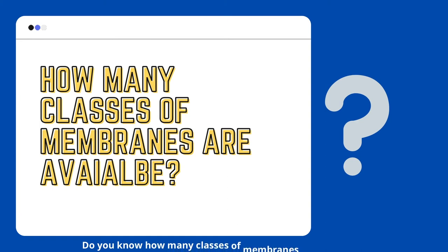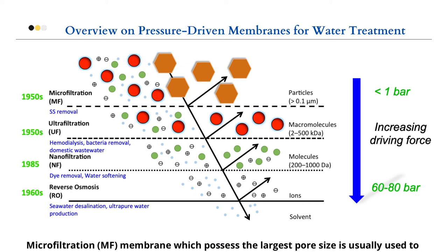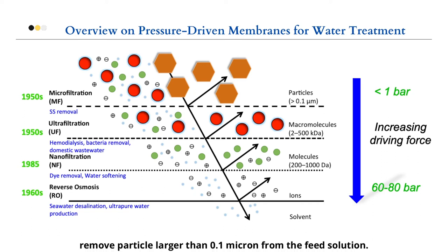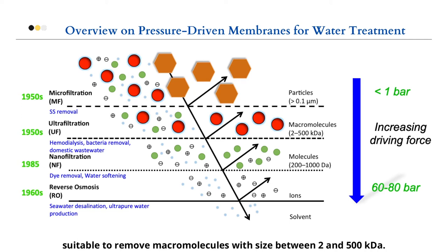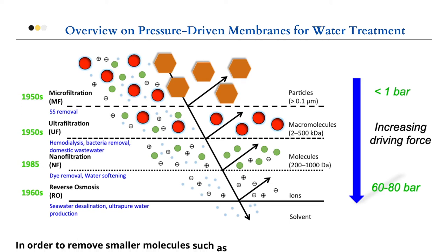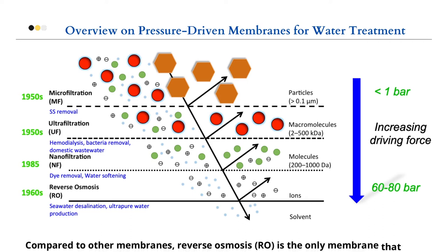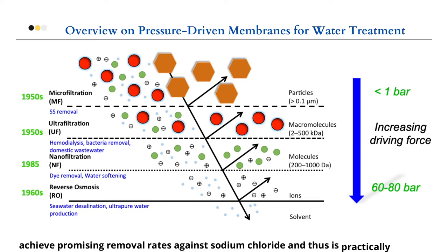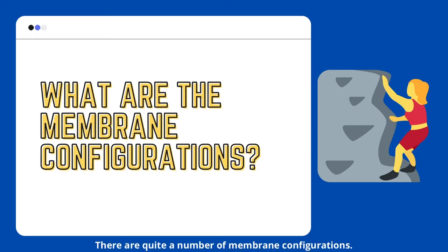Depending on membrane properties such as pore size, porosity, and hydrophilicity, several classes are used to differentiate these membranes. There are four classes of pressure-driven membranes in water treatment. Microfiltration membrane, which possesses the largest pore size, is used to remove particles larger than 0.1 micron from the feed solution. Ultrafiltration membrane, with a tighter pore size, is suitable to remove macromolecules with sizes between 2 and 500 kilodaltons. To remove smaller molecules such as dyes, micropollutants, and dissolved ions, nanofiltration membrane is employed. Reverse osmosis is the only membrane that can achieve promising removal rates against sodium chloride, and is practically used in brackish water and seawater desalination.